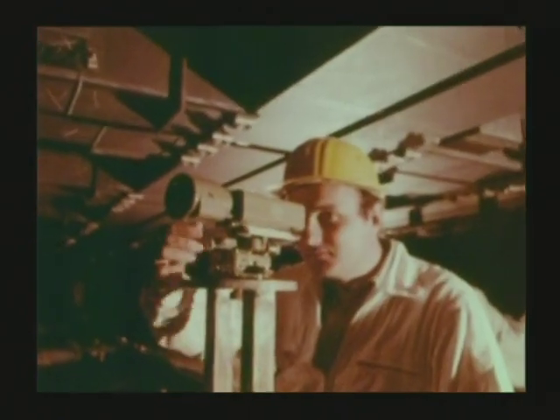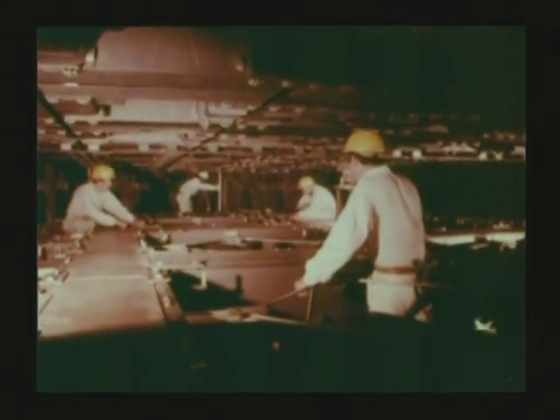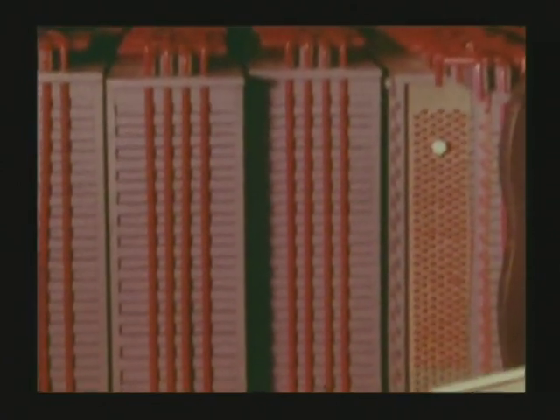The cells of the supporting apron, filled with graphite billets, form a radiation shield which, however, allows a free flow of gas. Beyond this shield, it is possible to gain access to the upper section of the exchanger in order to perform checks or repairs on the steam manifolds and on the upper part of the towers while the reactor is shut down. An access well makes it possible to go down the exchanger towers to the base of the vessel.